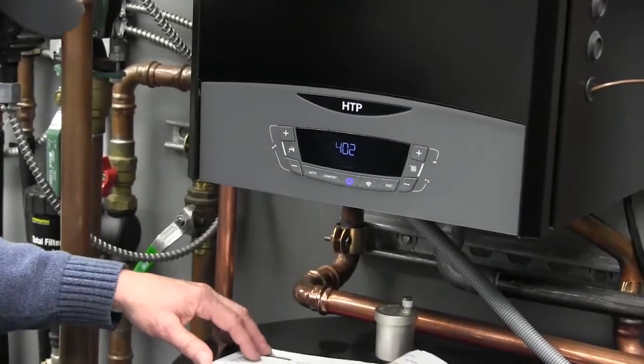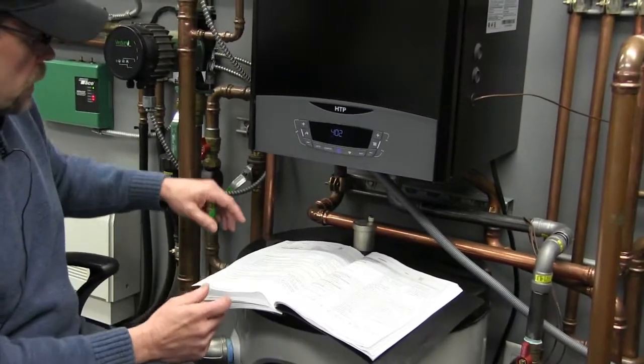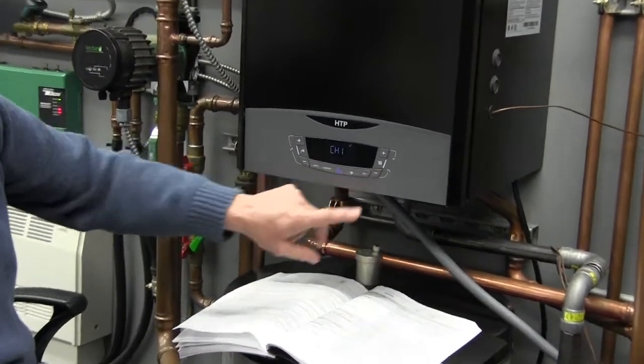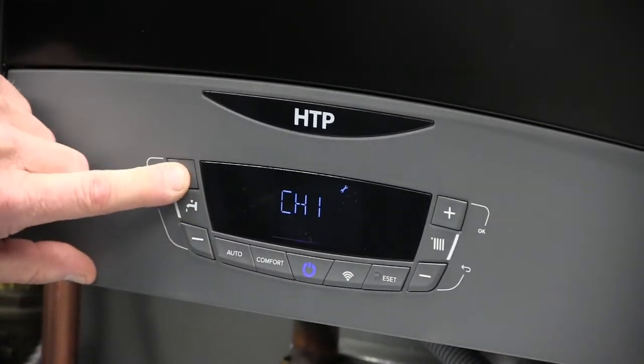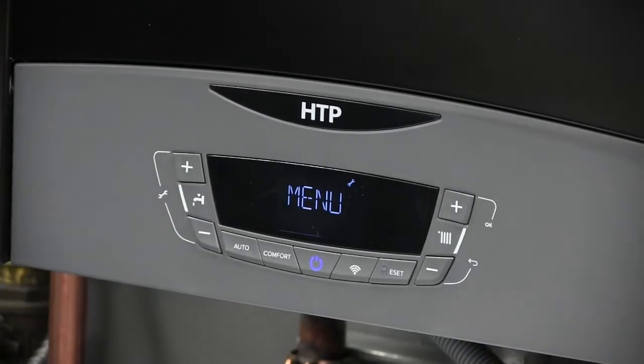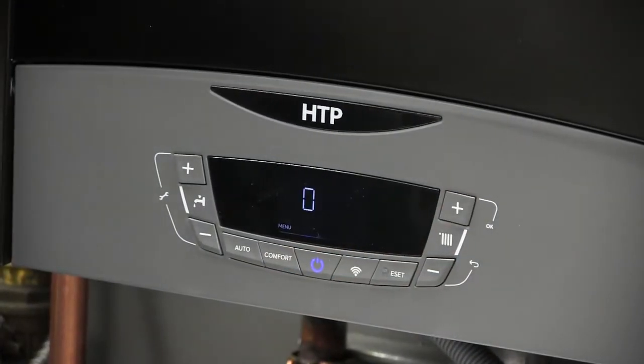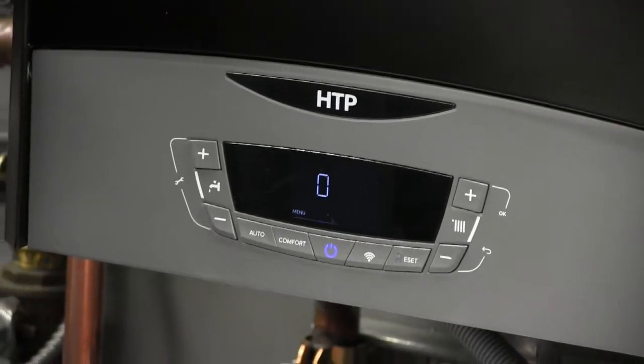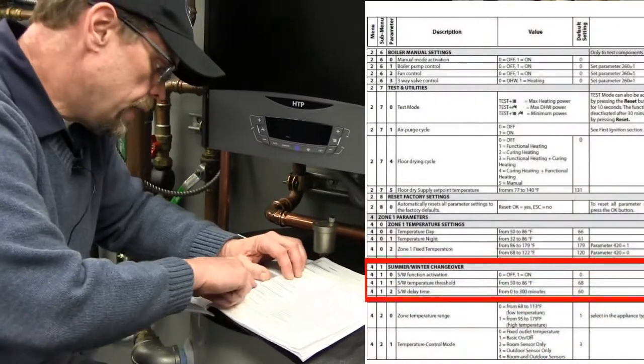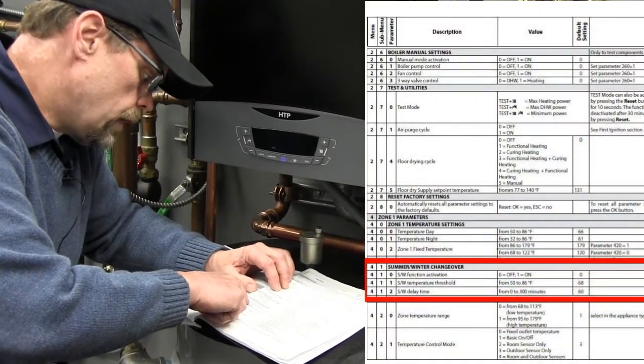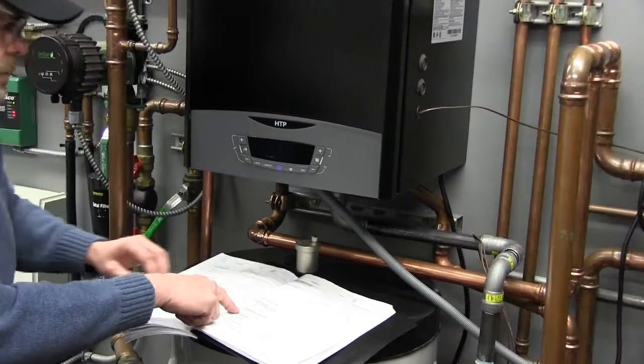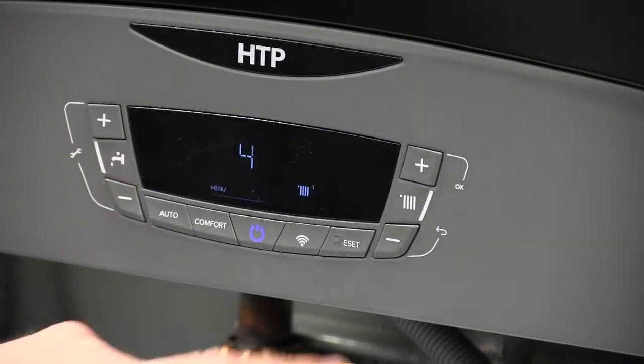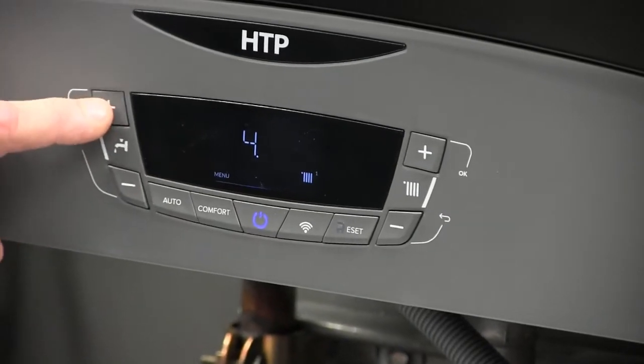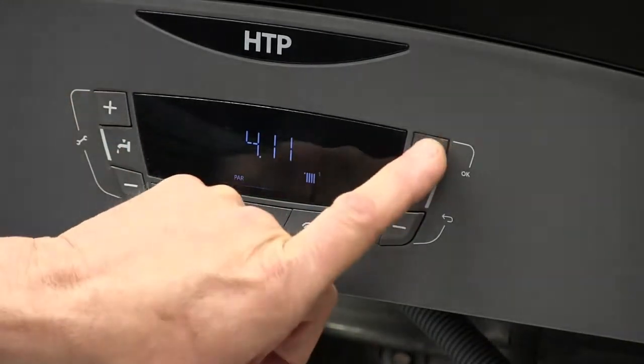Of course we know we would be in the 400 series, but to access the full menu, we have to go back to menu. And there's my menu. Hit OK. The way I'm finding the number is by going into the 400 series zone 1 parameters. Here it says summer winter changeover, and the temperature threshold is adjusted by function 411. So we go first to 4, okay. That moves us to the next number. 1, okay, and 1, okay.